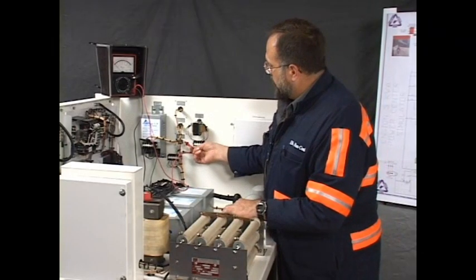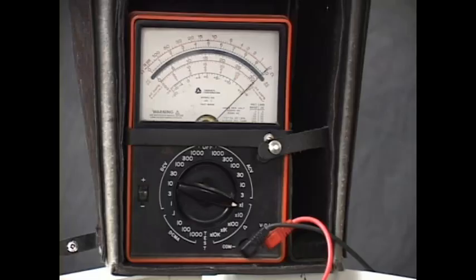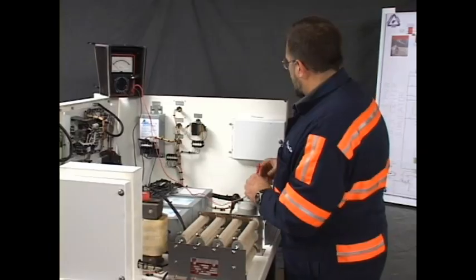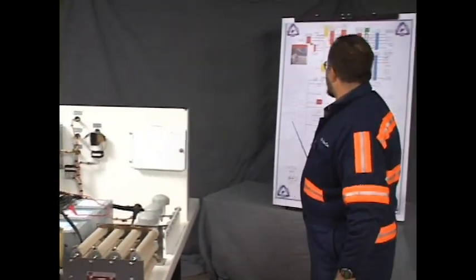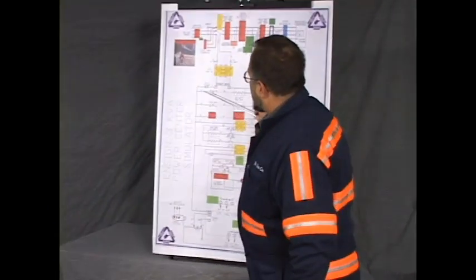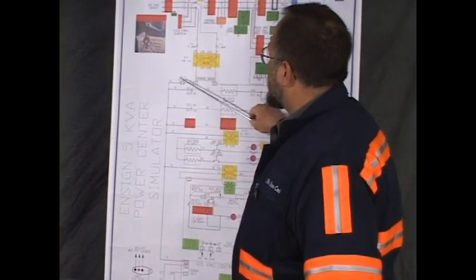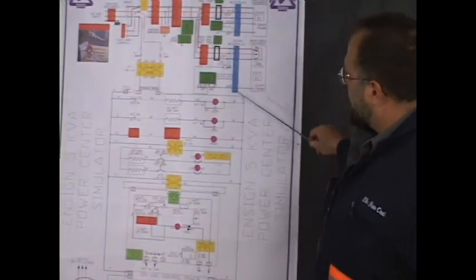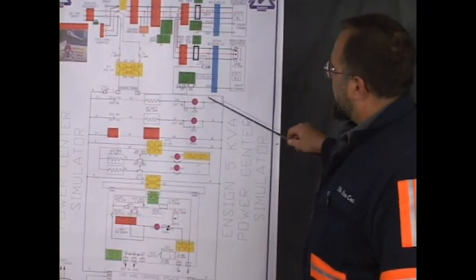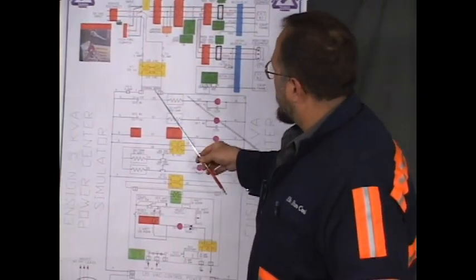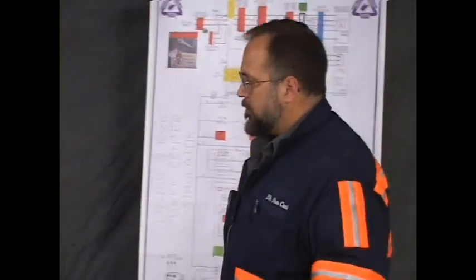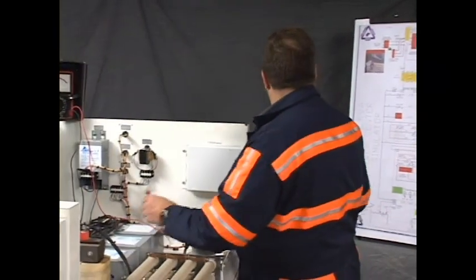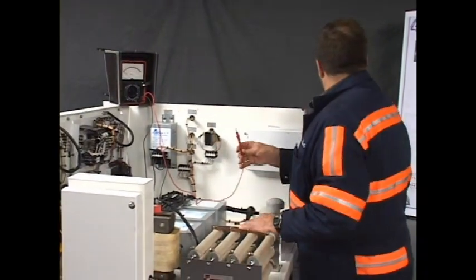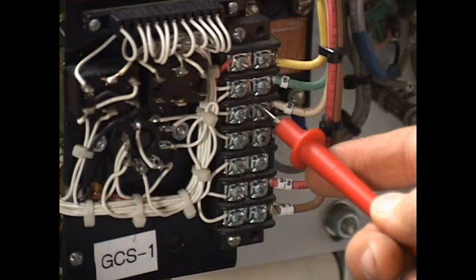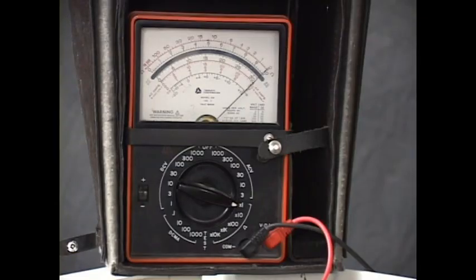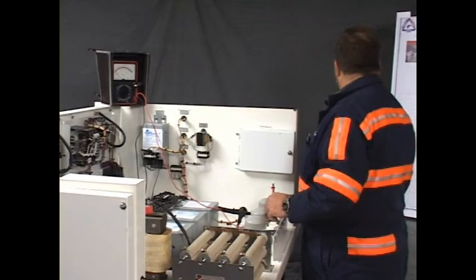The next point, the load side of FU1. At that point right there, wire number 7 changes numbers. It becomes 9. As you can see, 9 is common to all of the line side of this circuit, just as 8 is common to every rung of the return side of the circuit. Wire number 9 now. The next point that we can pick up on the machine to check for continuity would be terminal 1 of GCS1. As you can see by the meter, wire number 9 is intact. We have continuity to there. That's this point here.